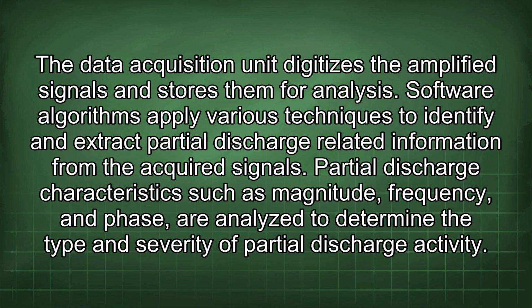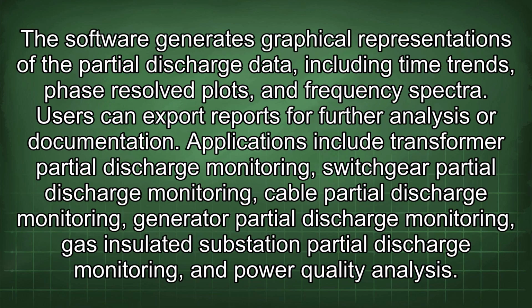Partial discharge characteristics such as magnitude, frequency, and phase are analyzed to determine the type and severity of partial discharge activity. The software generates graphical representations of the partial discharge data, including time trends, phase-resolved plots, and frequency spectra. Users can export reports for further analysis or documentation.